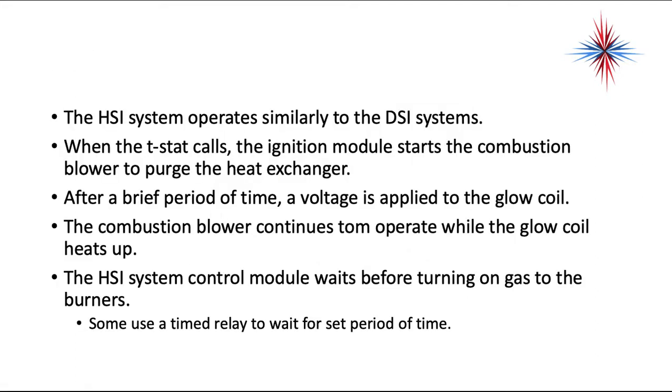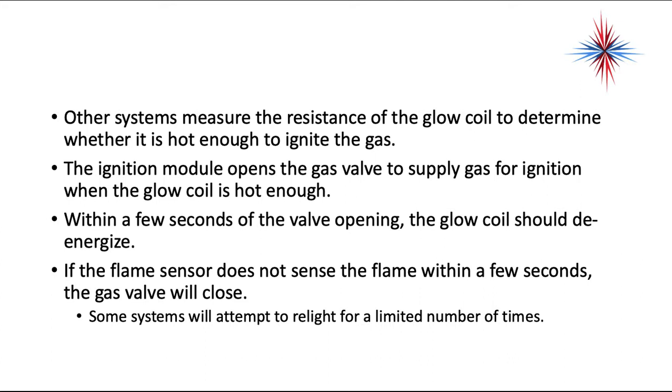The HSI system operates similarly to the direct spark ignition system. When the thermostat calls, the ignition module starts the combustion blower to purge the heat exchanger. After a brief period of time, a voltage is applied to the glow coil. The combustion blower continues to operate while the glow coil heats up. The HSI control module waits before turning the gas on to the burners — some use a timed relay, while other systems measure the resistance of the glow coil to determine whether it's hot enough. The ignition module then opens the gas valve. Within a few seconds of the valve opening, the glow coil should be de-energized. If the flame sensor does not sense the flame within a few seconds, the gas valve will close.